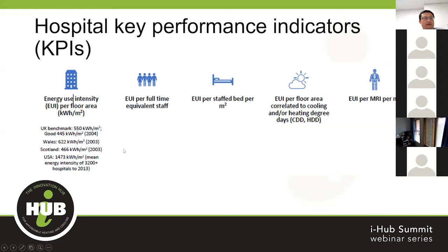We also can do EUI per full-time staff, or per staffed bed per square meter, or per floor area correlated to cooling or heating degree days, or per MRI per square meter, because MRI is actually quite a big power consumer.